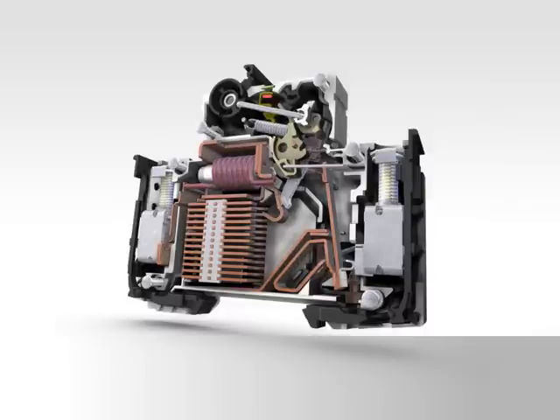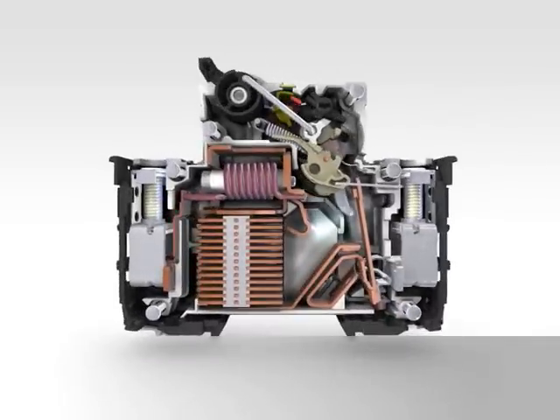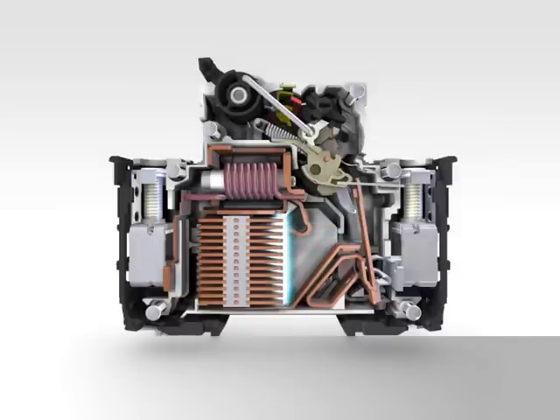A short circuit causes the switching contacts to open. This results in an electric arc, which passes over the discharge plate and the horn into the arcing chamber. Here it is distributed into small individual electric arcs. This isolates the affected circuit. This process takes roughly 3 to 4 milliseconds.